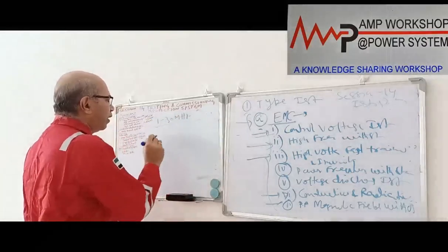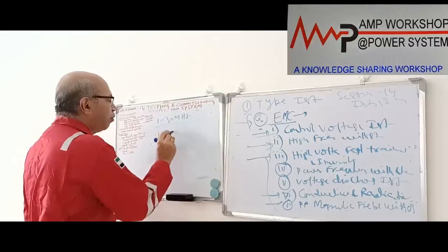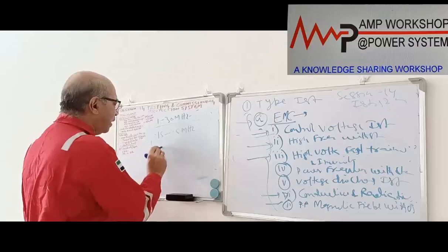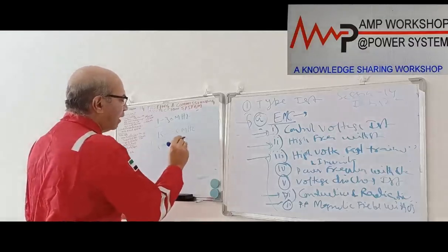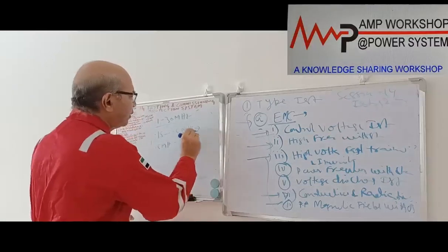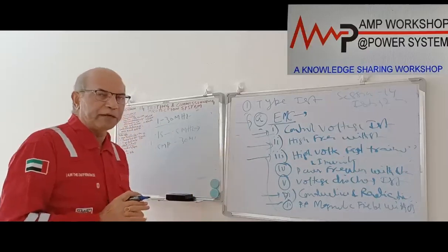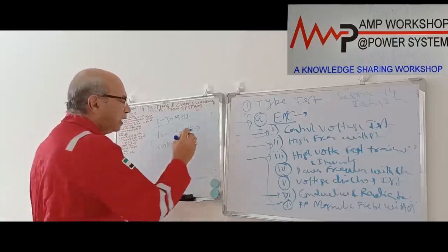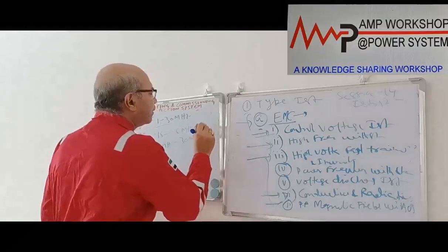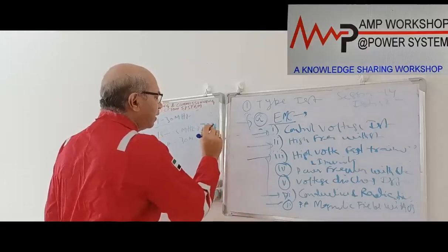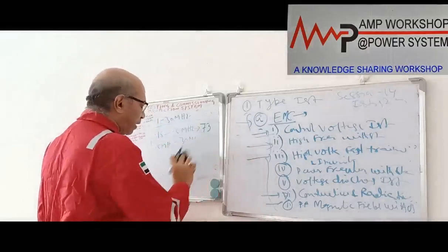It is split into two parts, 0.15 to 0.5 megahertz, this is one range, and 0.5 megahertz to 30 megahertz is another range. In this range, what do we do? The electromagnetic ambient which we create is 73 dB microvolt. This electromagnetic radiation is measured in dB microvolt.